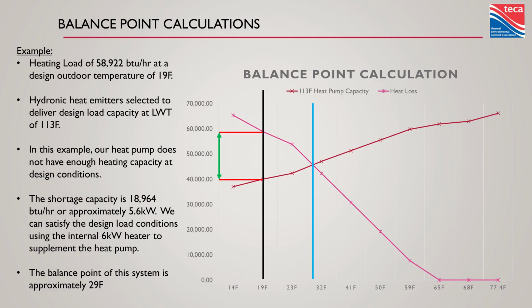Meanwhile, this is my heat pump. I get lots of capacity over here and less and less and less as the temperature drops. This blue line represents the balance point. That's the outdoor temperature where 100% of the heat loss can be met by the heat pump running at 100% capacity. Any warmer day outside than that, we can rely on 100% heat pump. Colder than that, we're going to need some help. How much? Connect the lines. There's our load. That's how much I get from my heat pump.